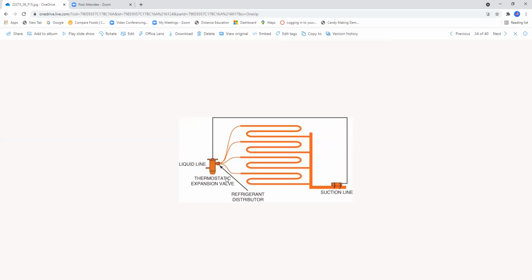Notice that we have 4 circuits on this particular design here. So on the outlet side of the TXV, you have a distributor, and these are capillary lines going to these individual circuits. We have 4 refrigerant circuits, and of course we have the suction line, which is over here, and the liquid line feeding the TXV over here.